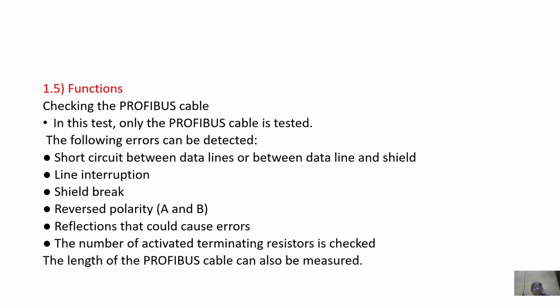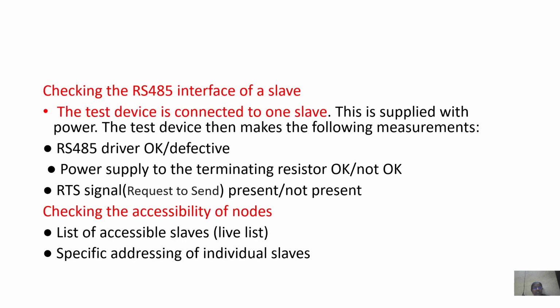So the functions: the following errors can be detected: short circuit between data lines, line interruption, shield break, reversed polarity, reflections that could cause errors. The number of activated terminating resistors is checked. The length of the Profibus cable can also be measured.